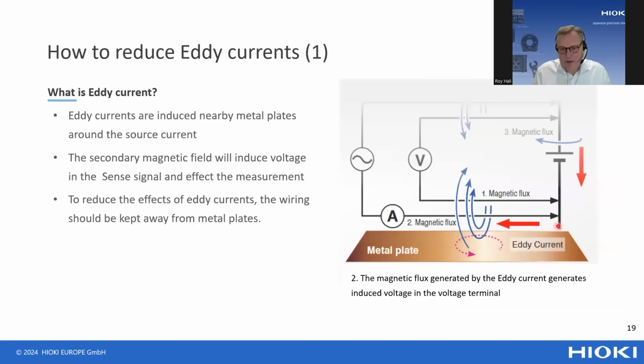Another influence on the measurement is eddy current, which is related to electromagnetic induction. The measurement current causes a magnetic flux, and this flux causes an eddy current in metal plates nearby the source current. That eddy current creates an additional magnetic flux, which is also picked up by the source or sense wire and interferes with the measured voltage over the battery. So it's related, but caused by metal plates very close to the source wire.